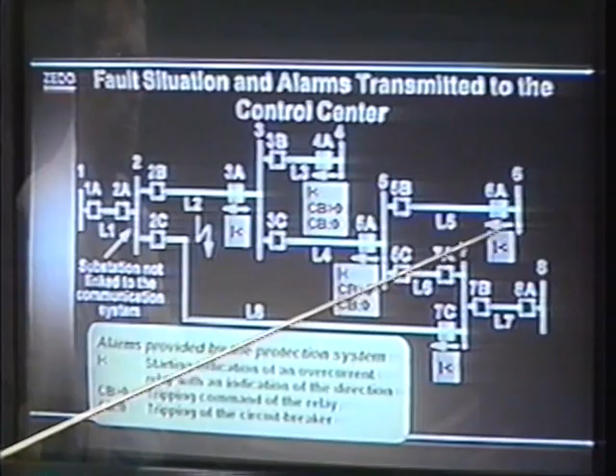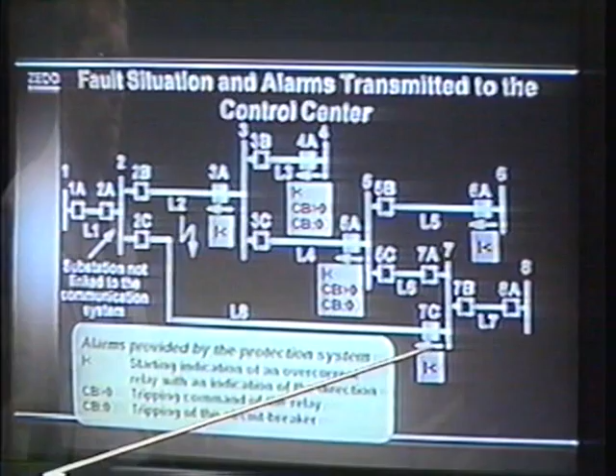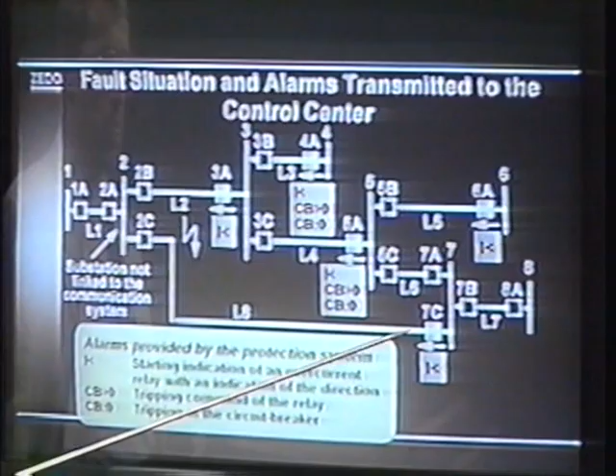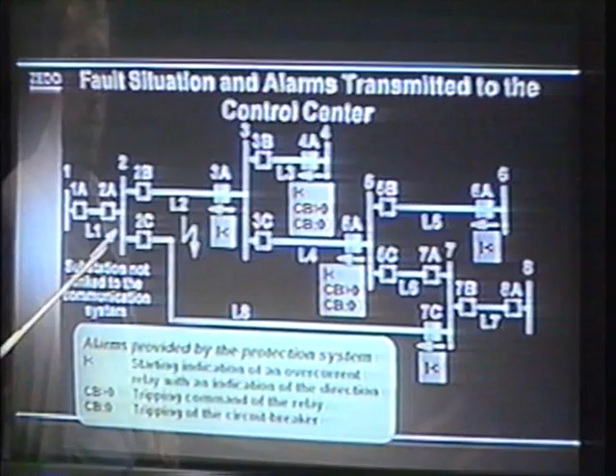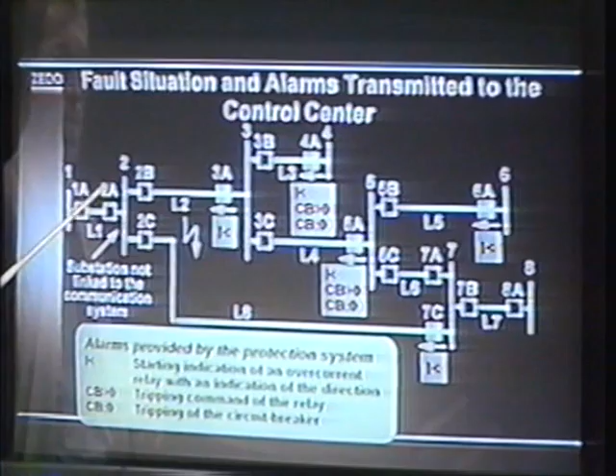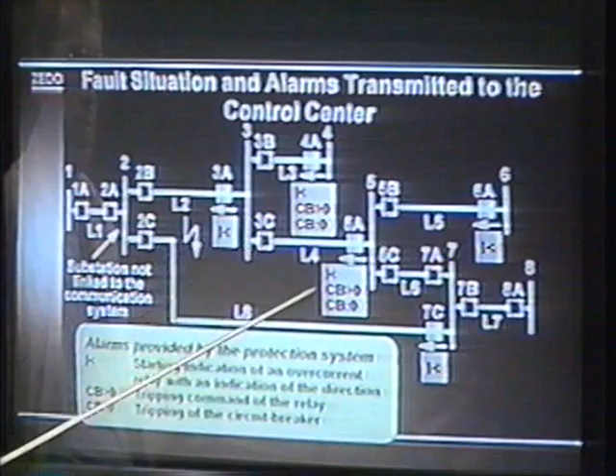Some other protection devices located at bus bar 6 and bus bar 7 did recognize the overcurrent as well, but they did not trip. At least we do not know whether they tripped the circuit breaker or not. It's important to know that bus 2, substation 2, is not linked to the telecommunication system, so we do not know anything from substation 2. And this is the situation. These alarms are used as input information for the device-specific artificial neural networks in the fault diagnosis process I would like to explain to you.